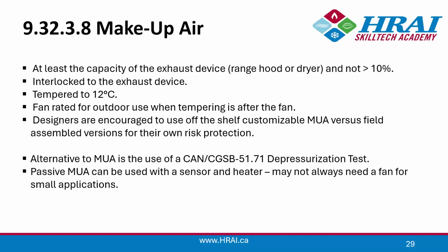And designers, of course, are encouraged, because all of this makes it sound like you invent this makeup air yourself and you specify all of the components. But actually, there are off-the-shelf customizable makeup air units available. And that's going to protect you from any risk of missing something in trying to put together some sort of field-assembled arrangement. So have a look, talk to the wholesalers, and get a couple of makeup air units for small systems. They have them from 100 to 600 CFM. Get those in your back pocket and specify those. That's the best way to go.